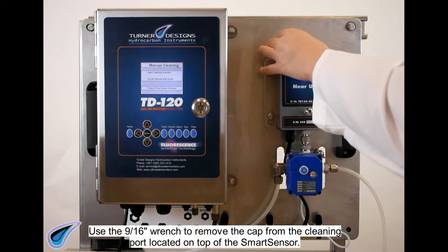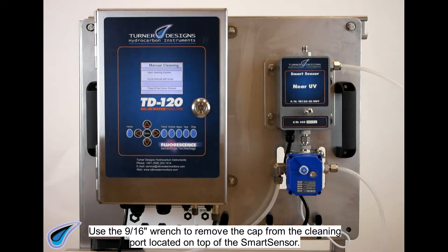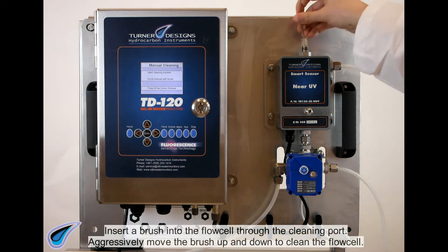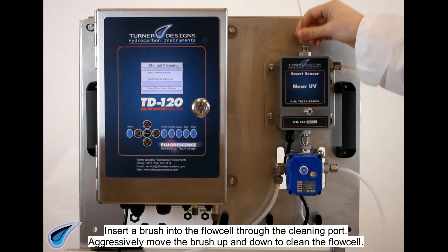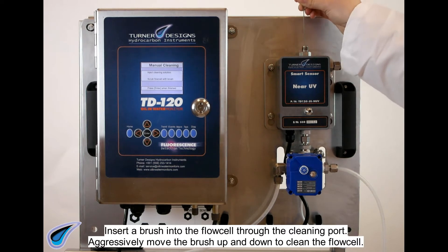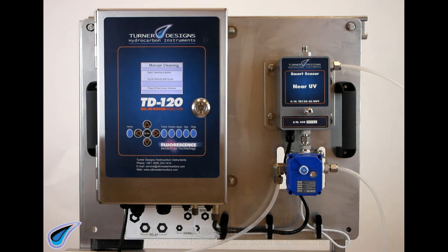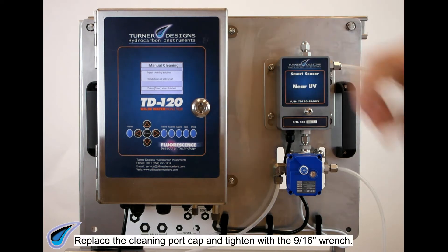Use the 9/16" wrench to remove the cap from the cleaning port located on top of the SmartSensor. Insert a brush into the flow cell through the cleaning port. Aggressively move the brush up and down to clean the flow cell. Replace the cleaning port cap and tighten with the 9/16" wrench.